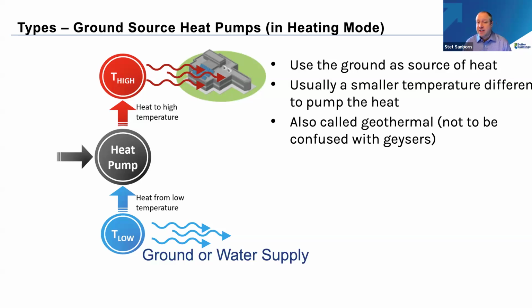We typically see in ground source heat pumps a much smaller delta T, or difference, between the ambient temperature in my building and the ground temperature. And so those systems tend to be, not always, but tend to be even more efficient than air source heat pumps, especially when we look at cold climates or extreme hot climates as well. Next slide.